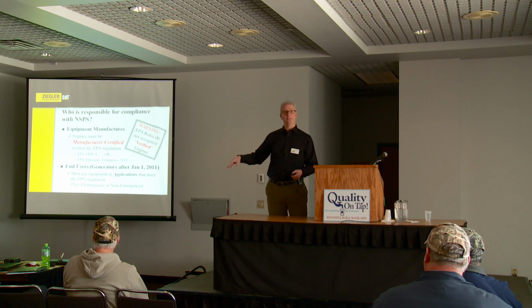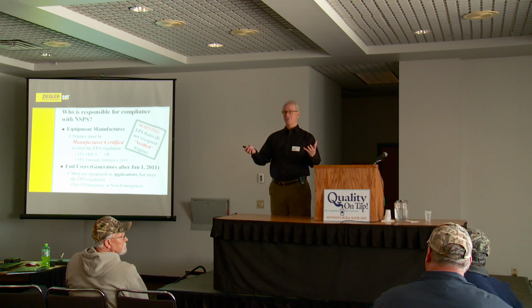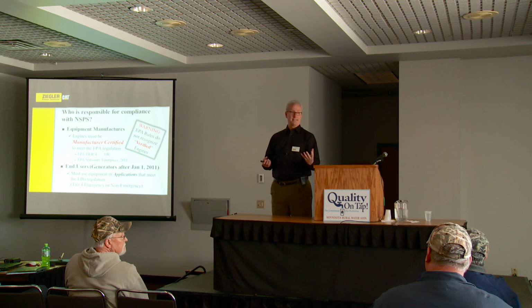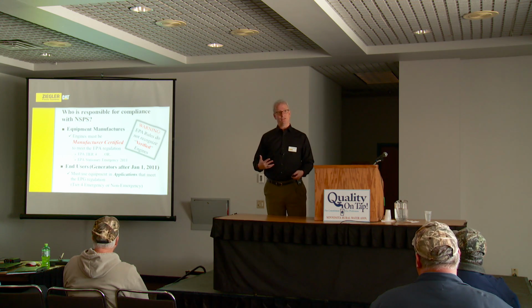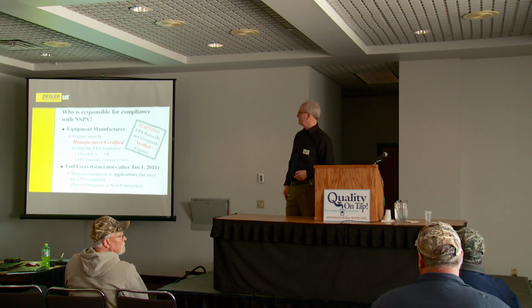But as of 2011, when you come to Ziegler to talk about buying a new diesel generator, one of the first things that we would say is, well, how are you going to use that engine? Are you going to be on your utilities peak shaving program, or are you going to just use it for emergency only? And the reason we ask that is because Caterpillar and the manufacturers have two different emission solutions engines that they are selling. Kind of the older, less clean engine, a Tier 2 engine for a big engine, or Tier 3 for a smaller one. And they can sell that to you today if you're just going to run emergency only per the rules. And then if you want to be on the utility peak shaving program, well, then you have to step up and get the cleaner engine, the Tier 4 engine.